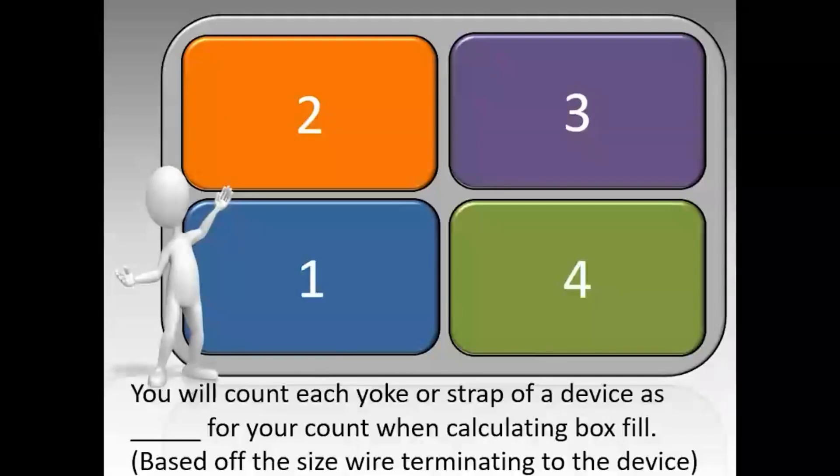So if you have a switch with 12 gauge wire to it, it's going to count as two 12s. If you have in the same box a switch with 14 gauge wire, that switch would count as 14s and the first switch would count as 12. And each yoke or strap of a device is going to count as 2 based off the size wire that's terminating to the device.